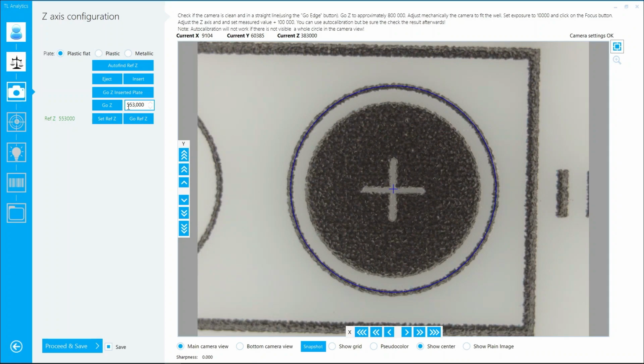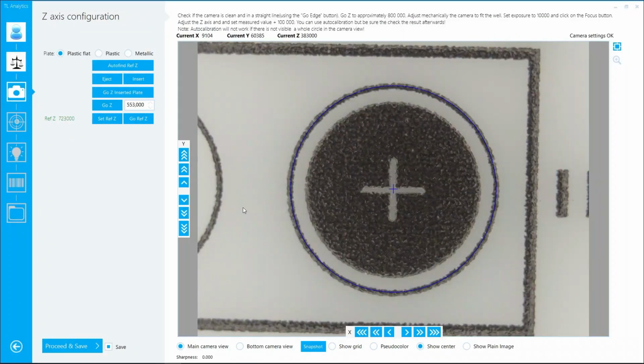So the result must be a sharp image and the blue circle is matching the circle on the plate. Also the cross must be centered nicely. So once your image looks like this, press Set Reference Z. Ignore this message. And this will save the coordinates, and then you press Proceed and Save. As you can see, after each step, the data will be sent to the device. Press OK.